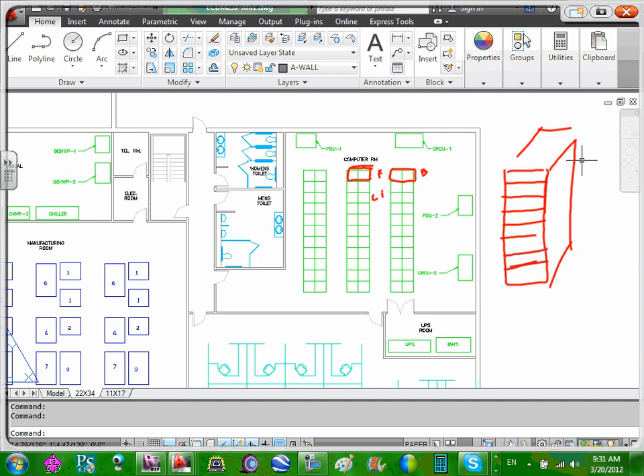So the perf tiles in the floor of this raised floor would be in the cold aisle. So we dump this aisle space full of cold air, and that puts the cold air through the racks into what we call a hot aisle. And then if this is dumping air out here, this also has to be hot, so then this side over here would be cold. And that's how we would be designing this, so that the front facing is in the cold aisle.